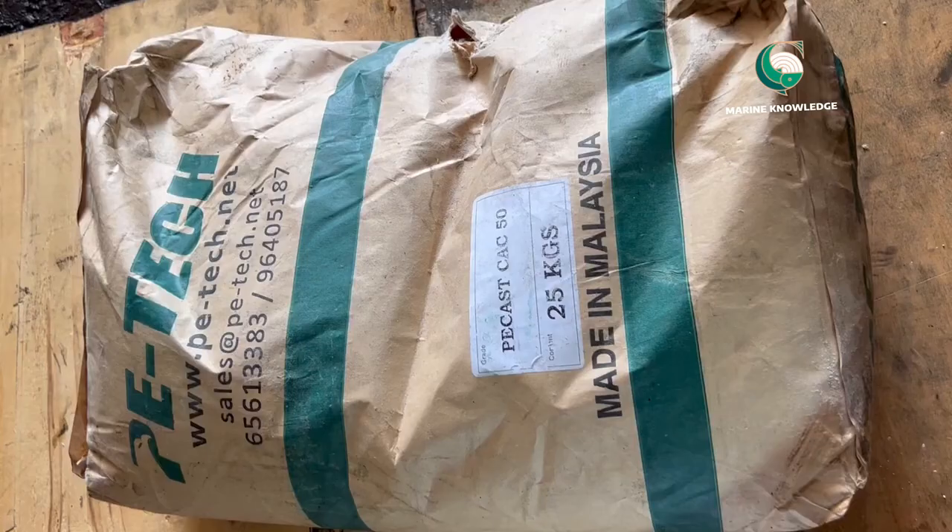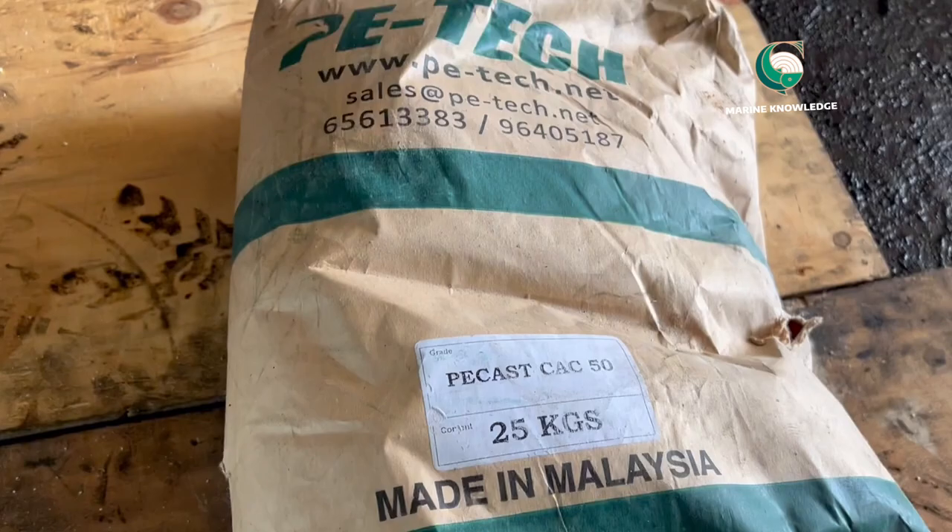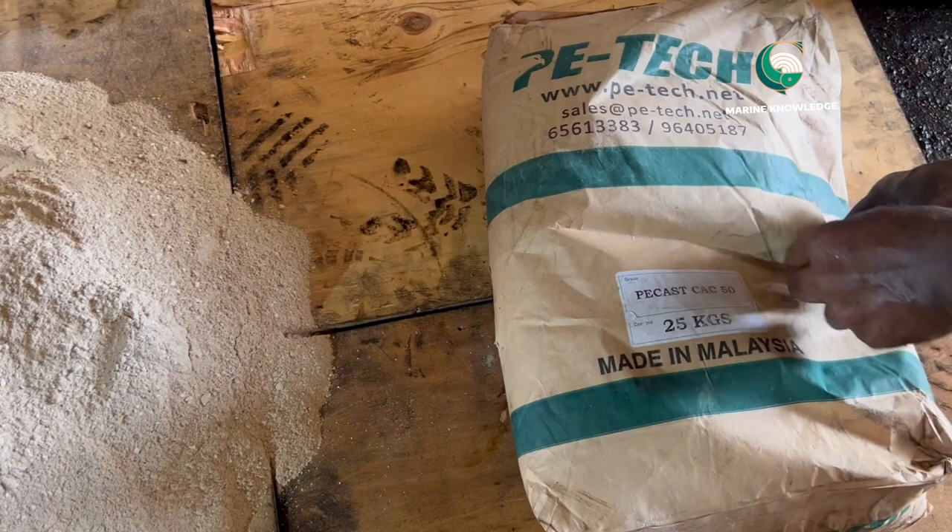You can see the refractory area is completely clean — no oil stains, no impurities, everything is fine. Inside the refractory area there are iron pieces called anchor bolts, and there is a pipe inside the furnace area called a drain pipe. We will put the refractories 15 centimeters below the drain pipe. We use the Pecast CAC50 refractory material.